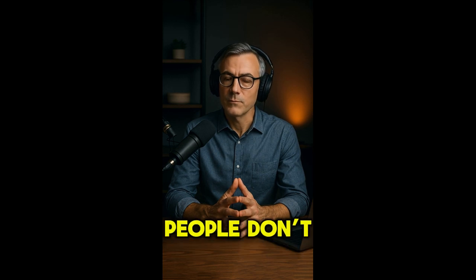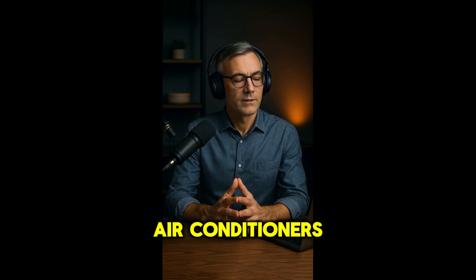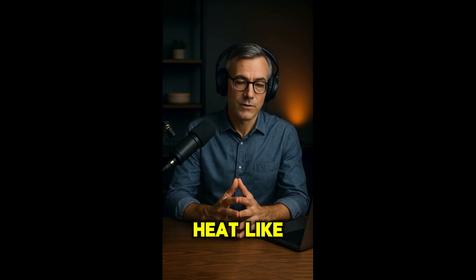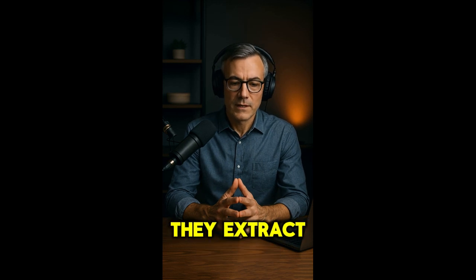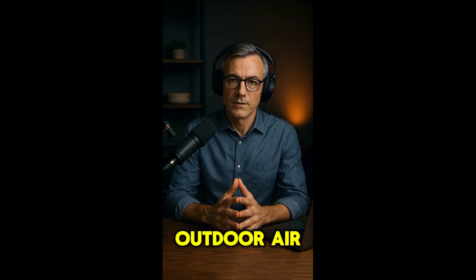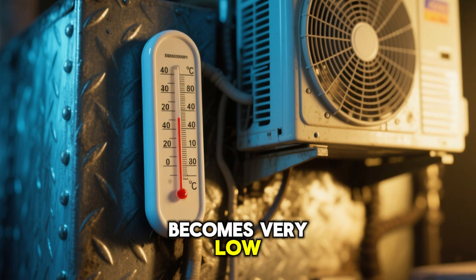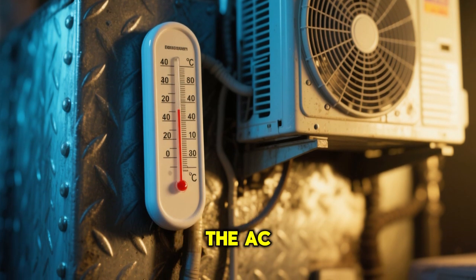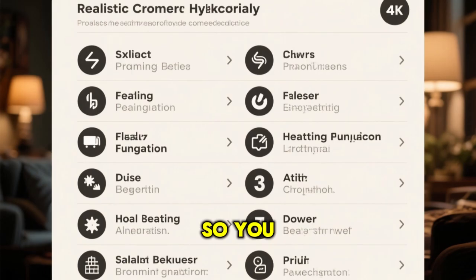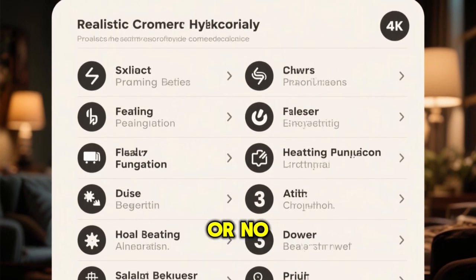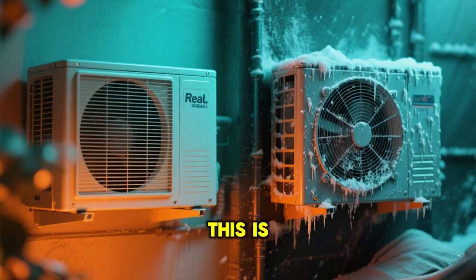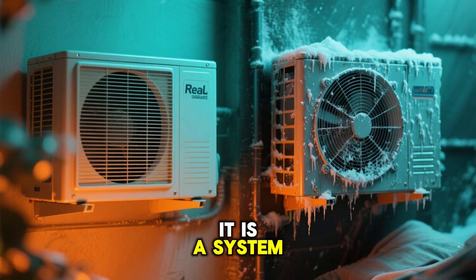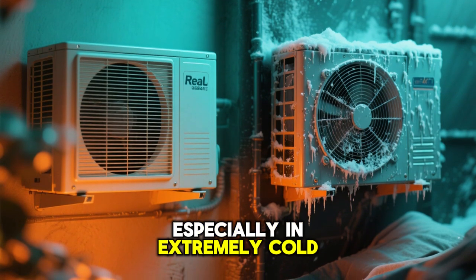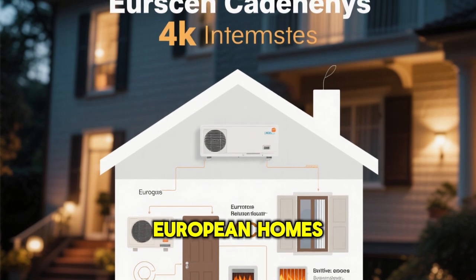Here is something most people don't know. Air conditioners do not produce heat like heaters. They extract heat from outdoor air. When outdoor temperature becomes very low, close to 0 degrees, the AC heating efficiency drops heavily, so you may notice weak, warm air, long heating time, or no noticeable heating at all. This is not always a fault. It is a system limitation, especially in extremely cold regions. That is why some European homes use additional heating systems with an AC.